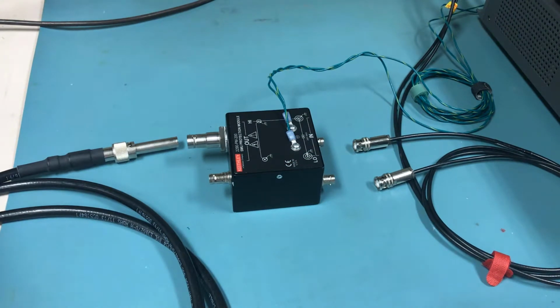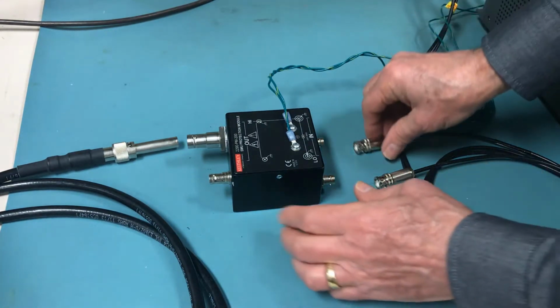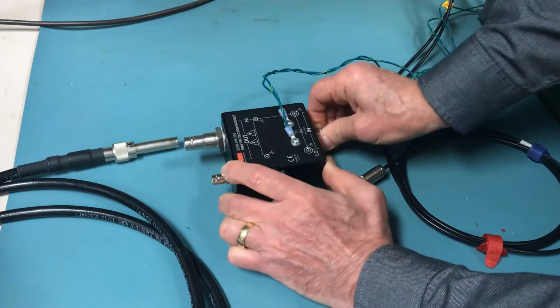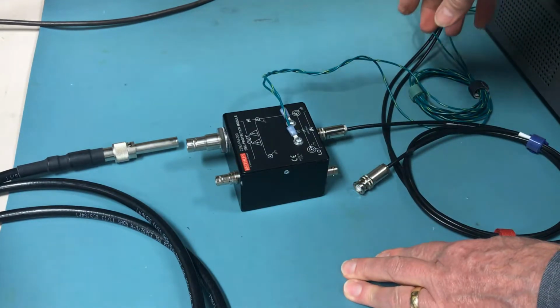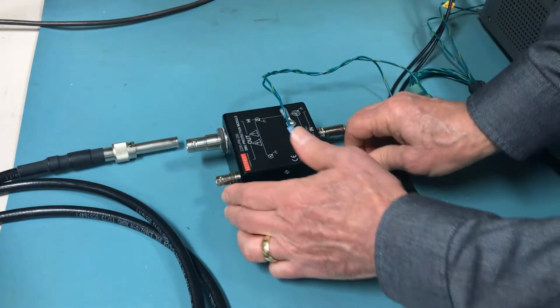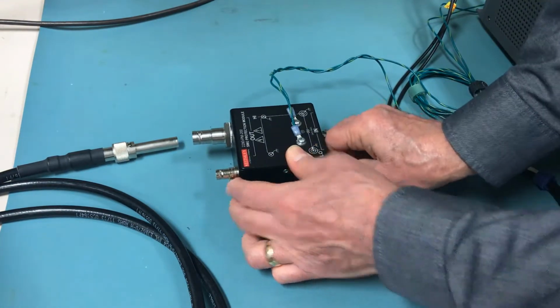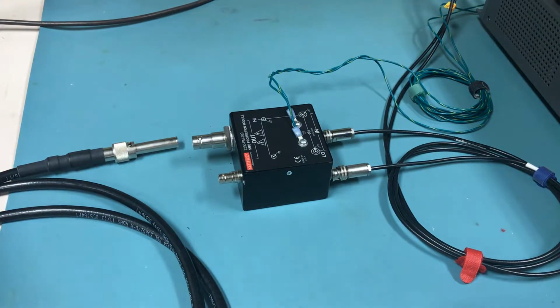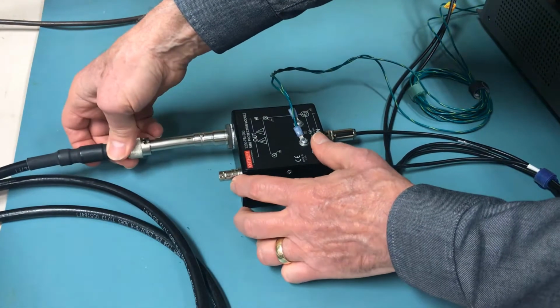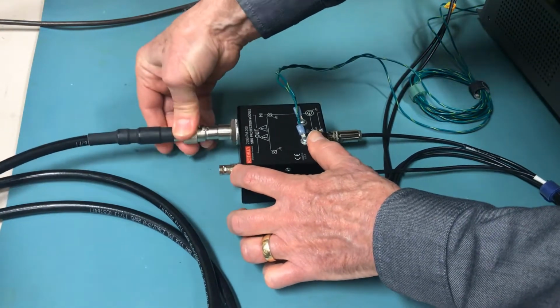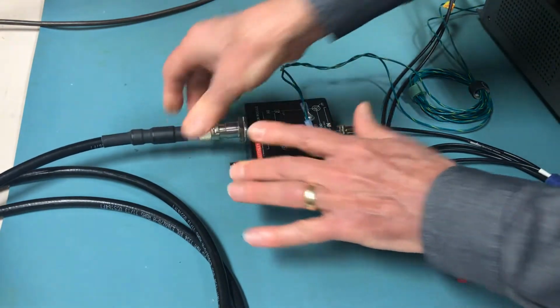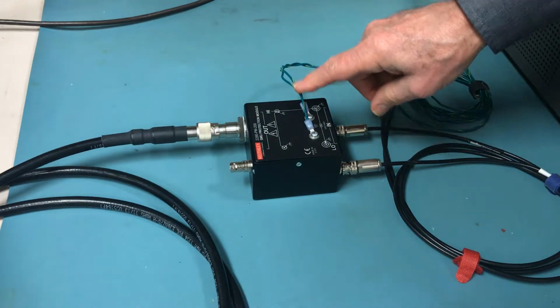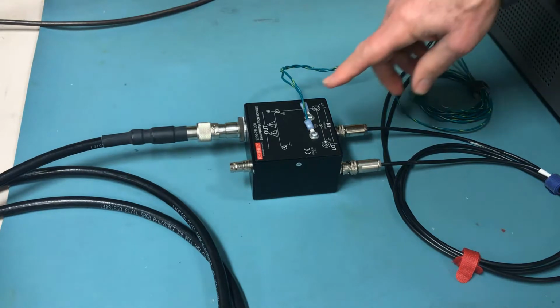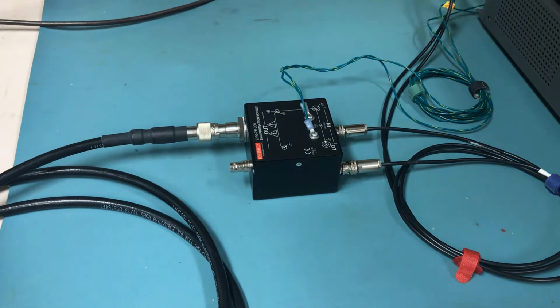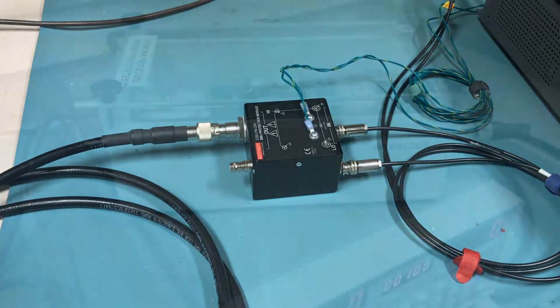All right, now we will connect the protection module to the circuit. I'm going to connect the high connector cable from the source measure unit to the protection module, and the low connection from the source measure unit to the protection module. Then on the high voltage side, I'll connect the 10 kV cable to the protection module, and I have already connected the green safety grounds from the protection module to a ground screw on the rear of the source measure unit.